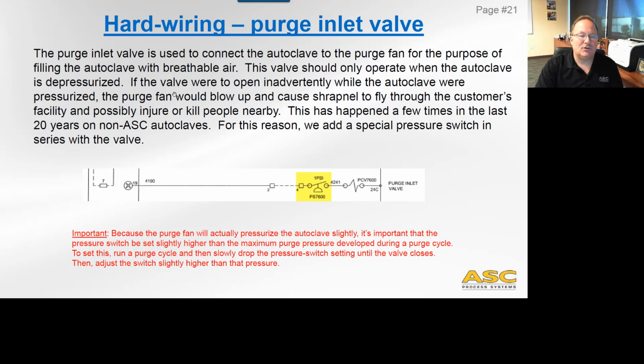This valve should only operate when the autoclave is depressurized. So basically, it's a big valve tied to the purge fan. If that valve were to open inadvertently under autoclave pressure, for instance, the autoclave pressure will come out of that valve so quickly that it will completely blow up the purge blower and throw pieces of metal everywhere, and that could actually kill people or definitely injure people around. This has actually happened a few times in the last 20 years on non-ASC autoclaves. They were not ASC control systems, but we heard about the aftermath, and there were very close calls. No one was ever killed or injured, but it could have been very bad.